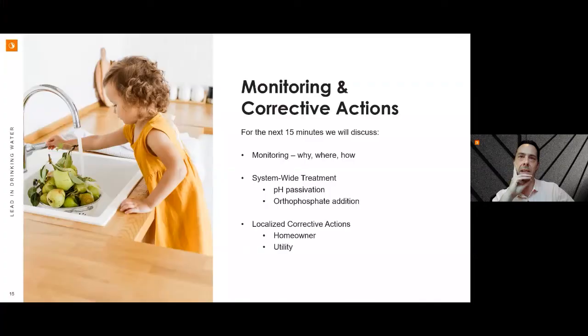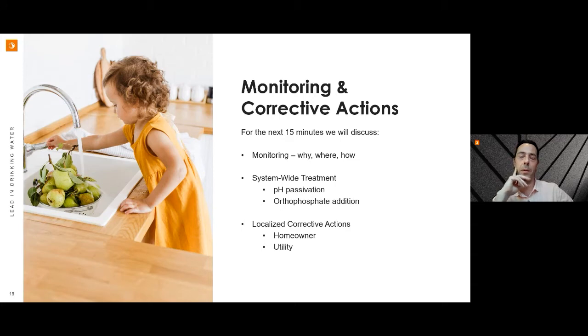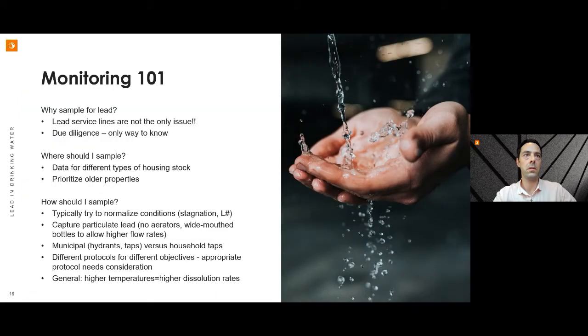Thank you, Leith. Over the next 15 minutes I'll talk about lead monitoring considerations, how to deal with elevated lead at a system-wide water treatment level — specifically pH passivation and phosphates — and localised corrective actions that homeowners and utilities can undertake. Looking first at monitoring: we need to sample in order to understand if drinking water reliably and consistently has elevated lead, which we might define as greater than the MAV of 10 micrograms per litre. Lead service lines are not the only issue. As the standards have come down, other lead-bearing fixtures like brass are also contributing to exceedances.